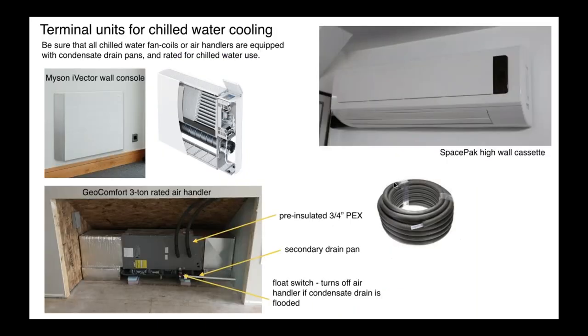You've got choices for indoor. Myson makes a nice unit here, and some other companies do as well. Make sure you have a drip pan. Don't just assume that any console or any air handler can work with chill water. That coil is going to get wet, and on a hot, humid day, you're going to produce several gallons of condensate. And if you don't have a drip pan, it's going to be a real mess. So make sure you have a drip pan in it.